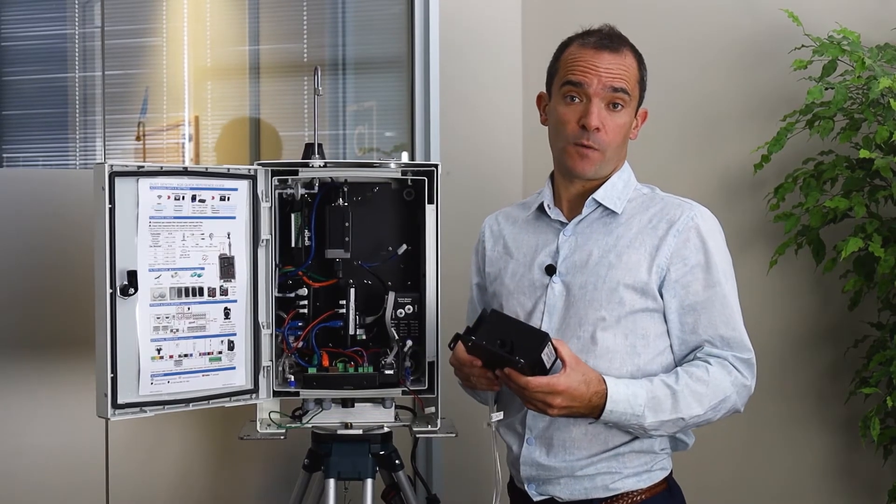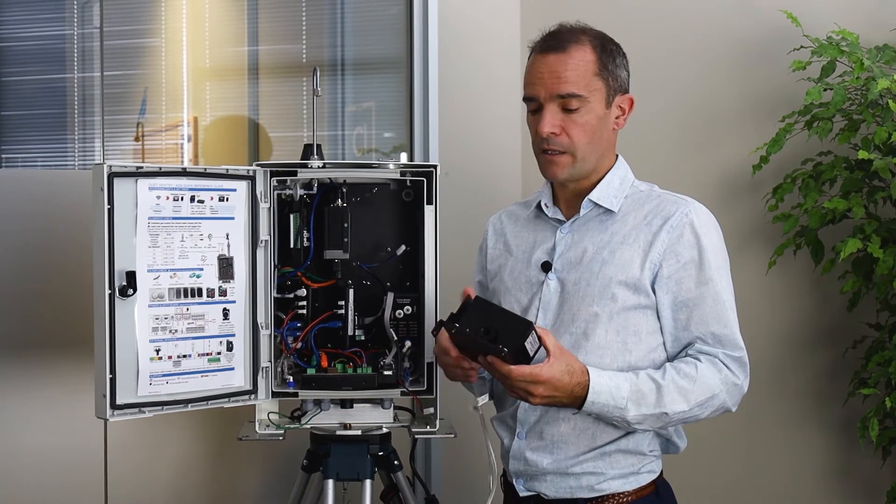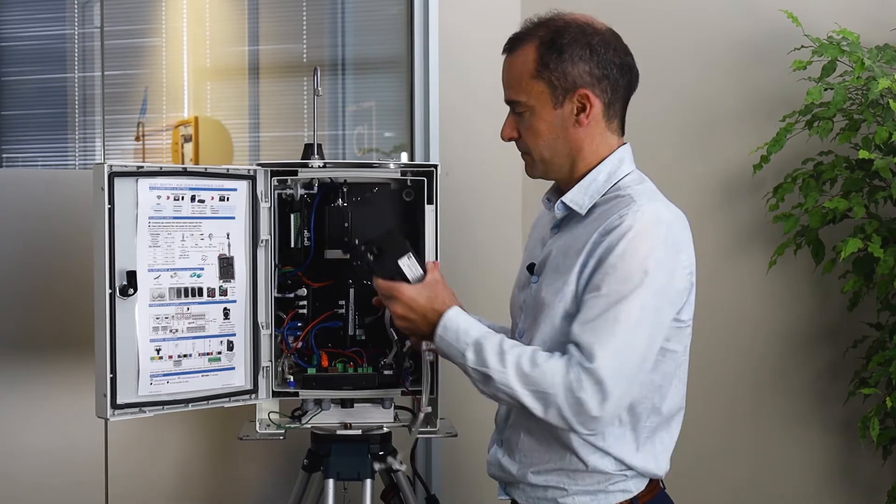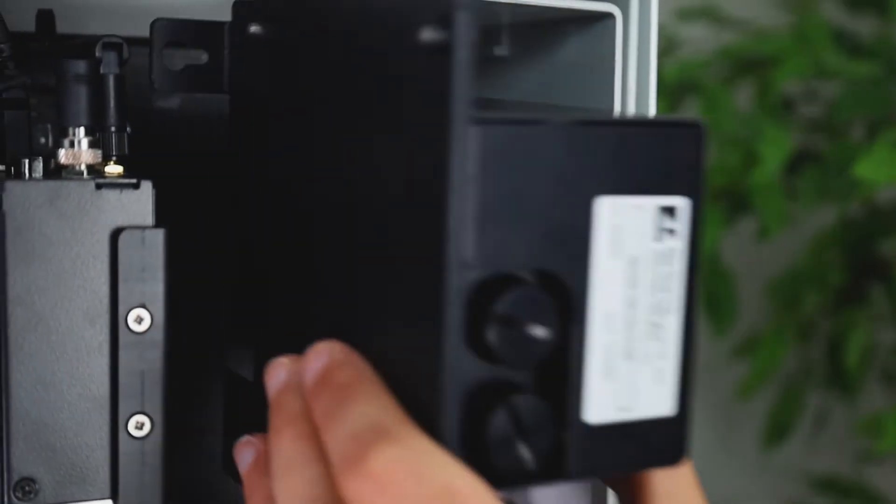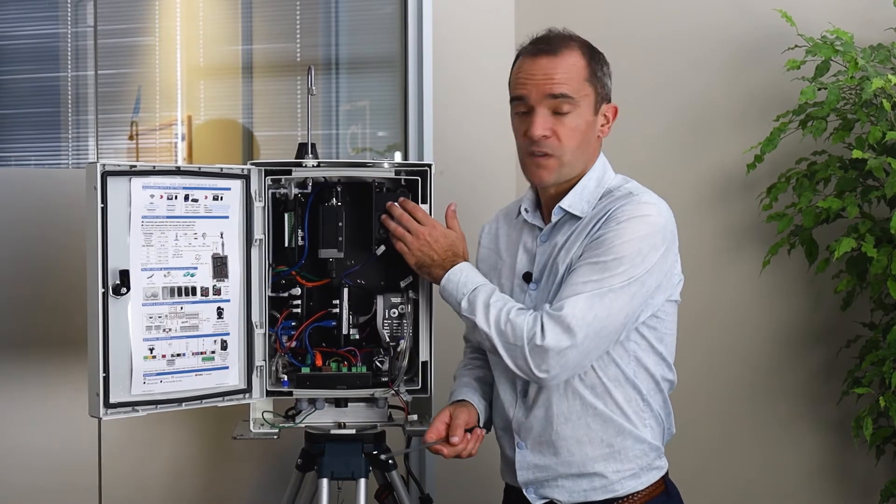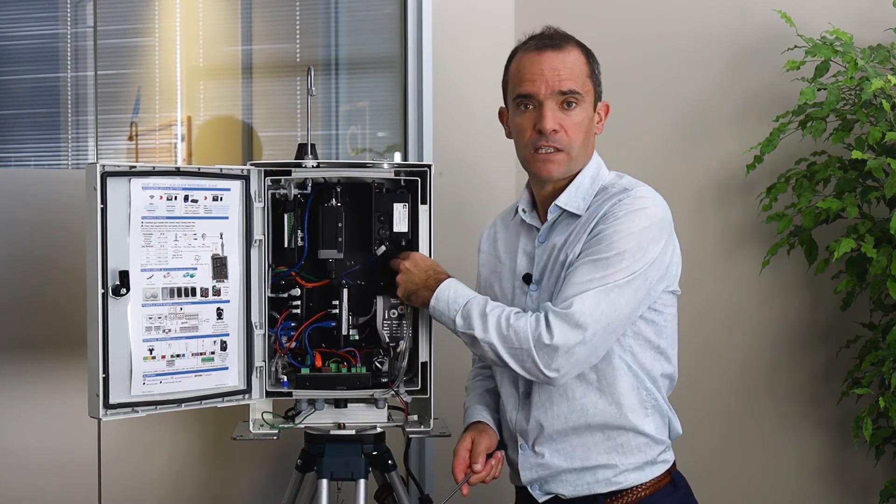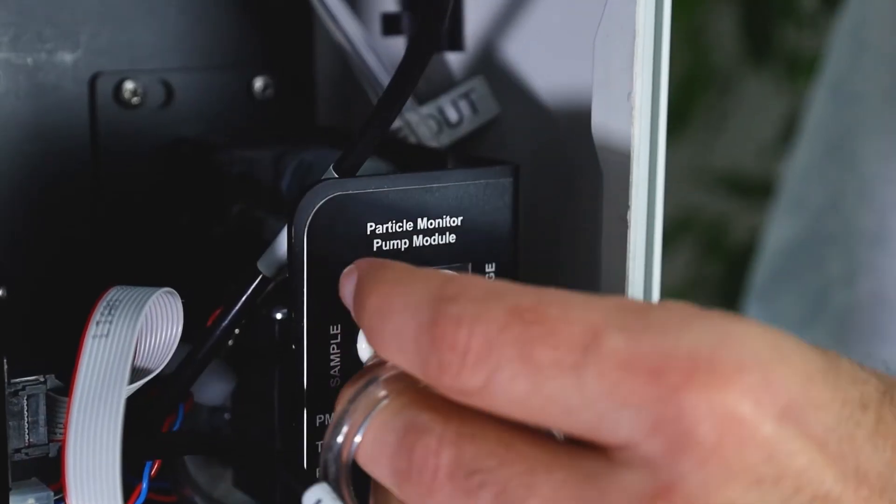You will have received your hot swap engine in the courier mail. Now it's just a case of doing that process in reverse. Once you've reinstalled the engine using the three retaining screws, you have the two plugs that need to be put back and the connections to the pump module.